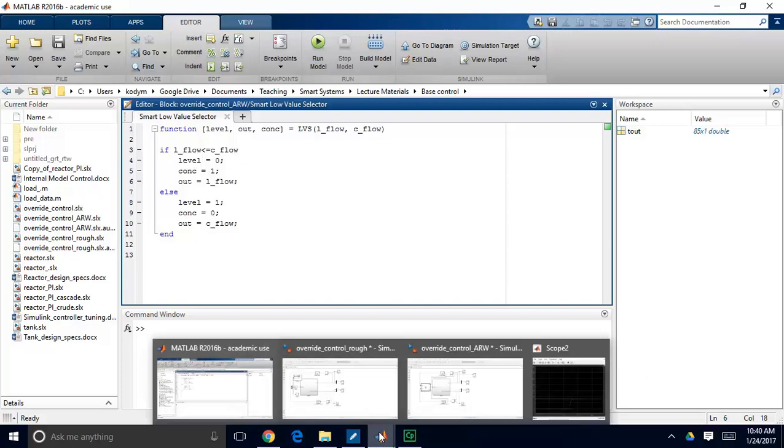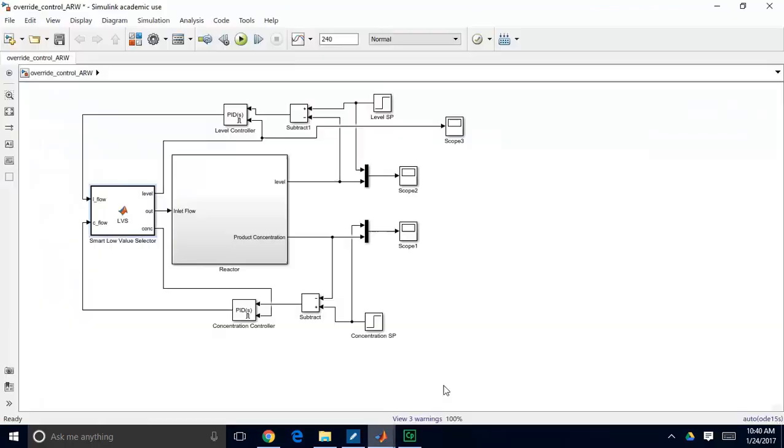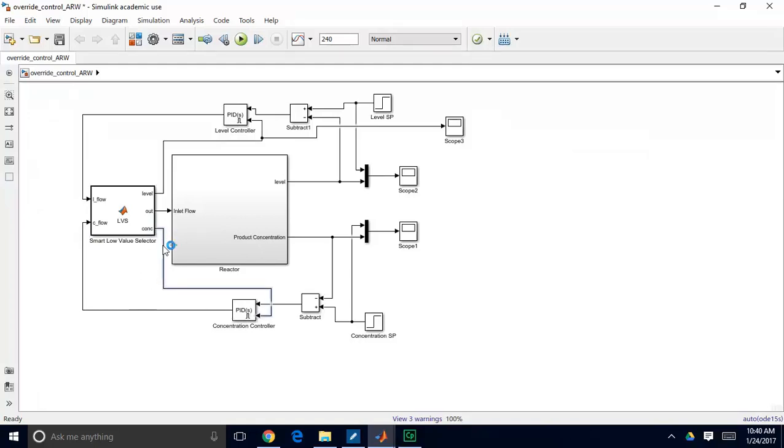So if you go back, so when we're in level control, this level variable is zero and the concentration variable is one. And what that does to our overall system is when we're in the level control, I want to send a zero value to this controller, which means it will keep integrating and the controller will continue operating as normal. The concentration controller, which would be the one that's not in control, I'm going to send it a signal of one, so I'm going to send it this non-zero value, which tells this concentration controller to stop integrating. So it's not in control, so there's no use in having this integral error build up over time.